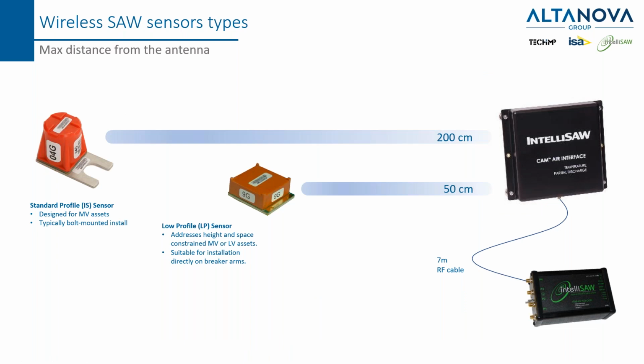So the question is, how far can we go with these sensors, since they rely on wireless technology? There is not only one type of sensor, there are several types. Basically, the working principle and the technology inside are the same, but they differ according to size, because inside the medium voltage compartment there can be size and dimension constraints. So in order to satisfy this requirement, the company has designed different sizes of this sensor. The standard profile wireless sensor is typically mounted under the bolt, and covers up to 2 meters distance from the antenna interface.